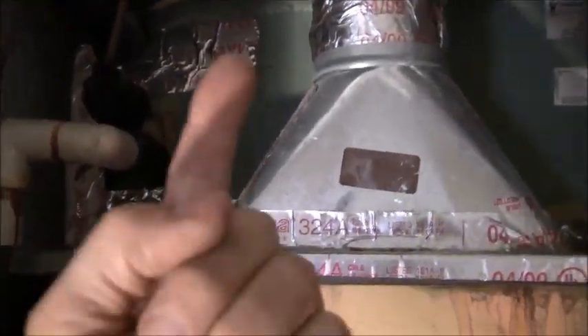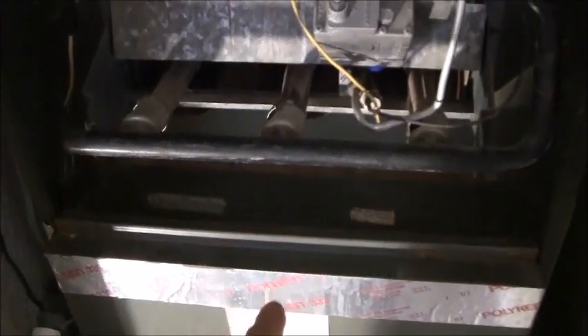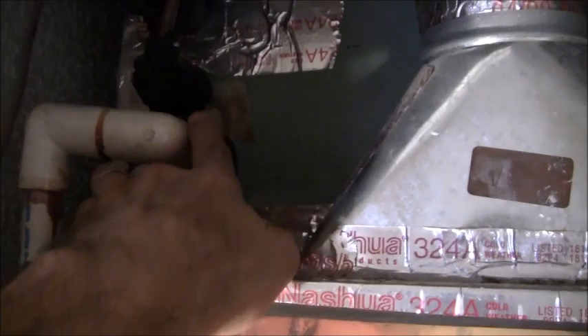If this was in the basement, some systems drain to a small condensate pump located at the base of the furnace. Then they go out. Every house is different, okay? This house, no condensate pump, just gravity drain. They did not put a P-trap in, which is not terrible because the evaporator coil is on the downstream side of the blower fan motor. So this is a positive pressure here, so a slight amount of pressure is going to bleed out of here and out with the condensate.